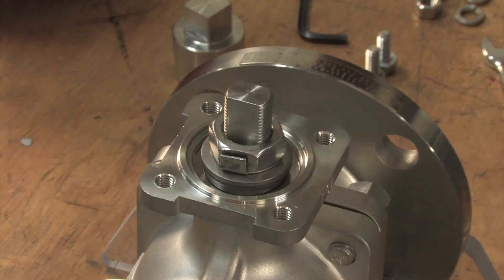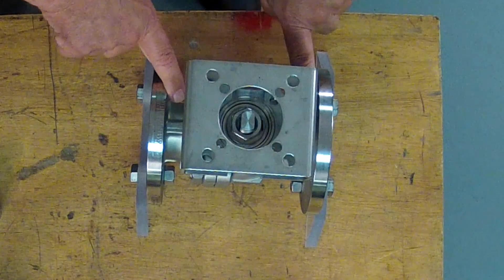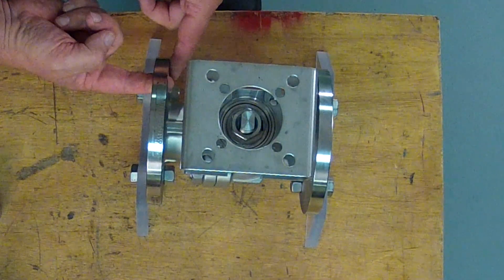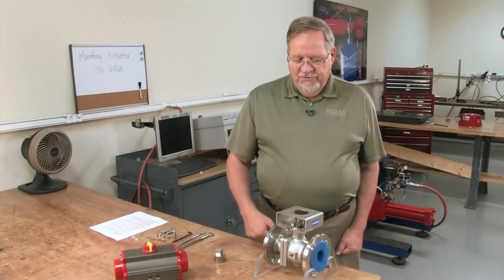Then we want to take the bracket, make sure it fits on the valve and doesn't hit the flanges. On smaller valves where the mounting pads are below the mounting surface, we want to make sure that the flange bolts don't get in the way of the mounting brackets so it can be installed later in the field.